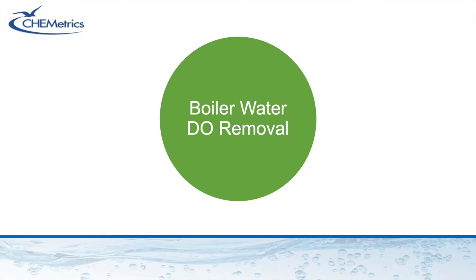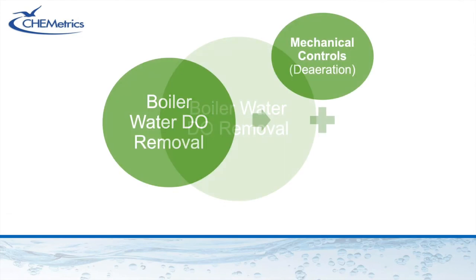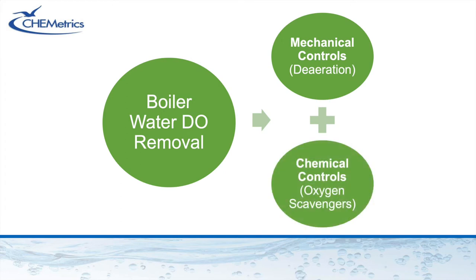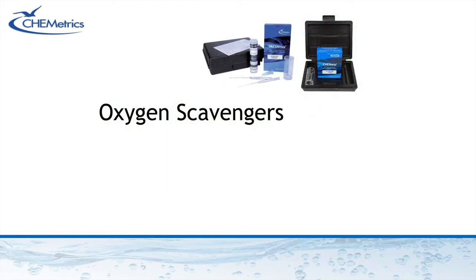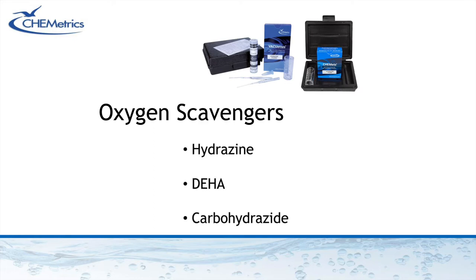There are two primary methods that boiler operators use to reduce dissolved oxygen: mechanical controls and chemical controls. Mechanical de-aeration, commonly the first and most economical technique, can reduce DO levels down to around 10 parts per billion. Plant operators can also employ chemical treatment using oxygen scavengers like hydrazine, DEHA, and carbohydrazide to consume the remaining DO, and CHEMetrics offers tests for these analytes.